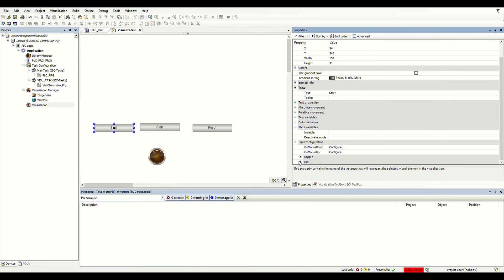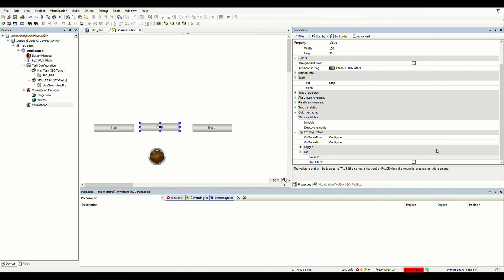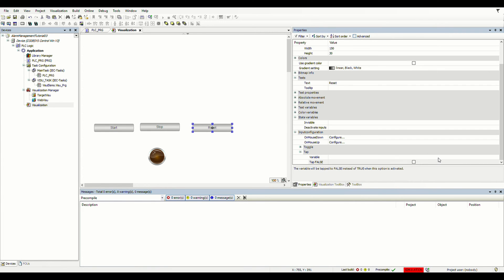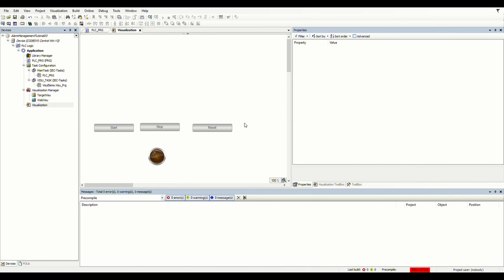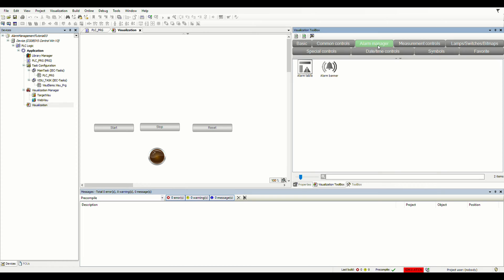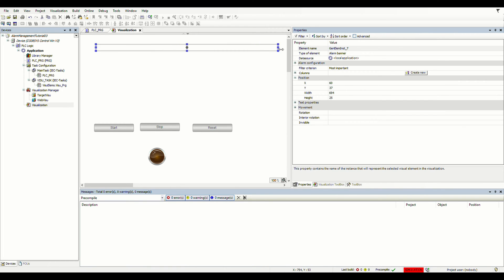For the start button, we set the variable PLC_PRG.start, meaning that when the start button is pressed that variable will be true, otherwise false. For stop, we do the same for the stop variable — stop will change the value of the stop variable. And reset will do it for the alarm reset variable. We also have two different elements in the alarm management group in the visualization toolbox.